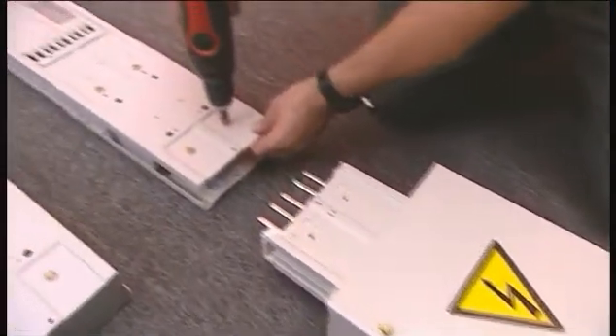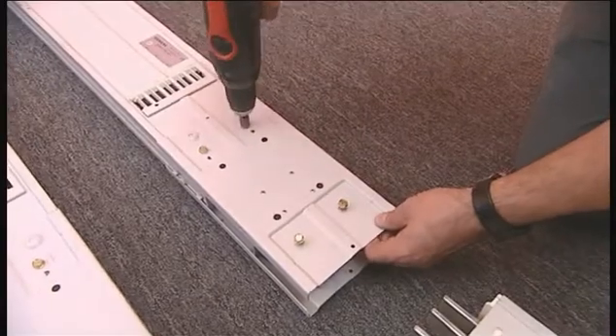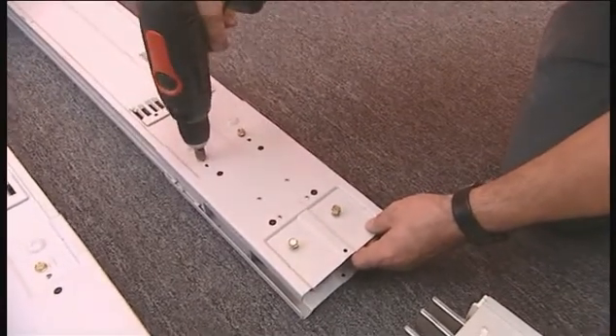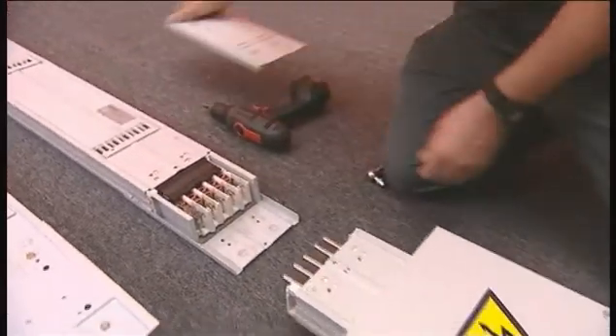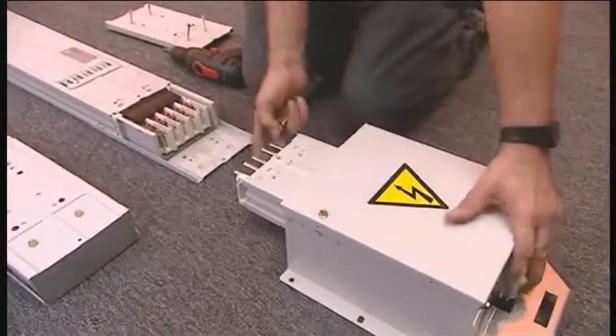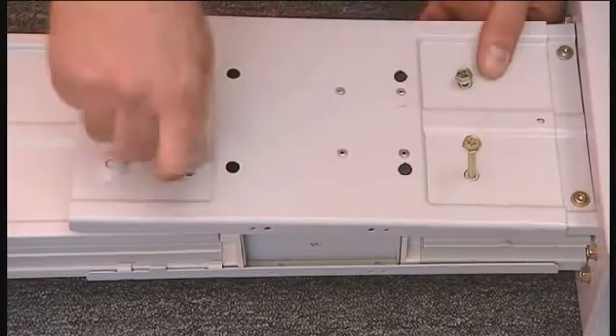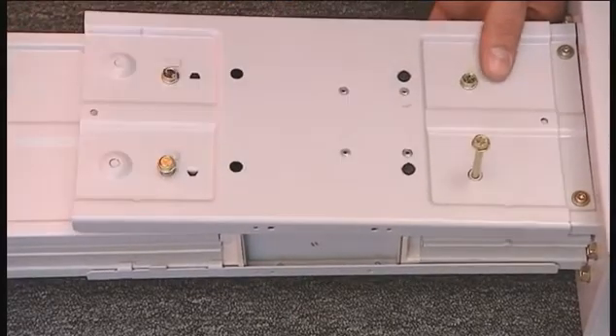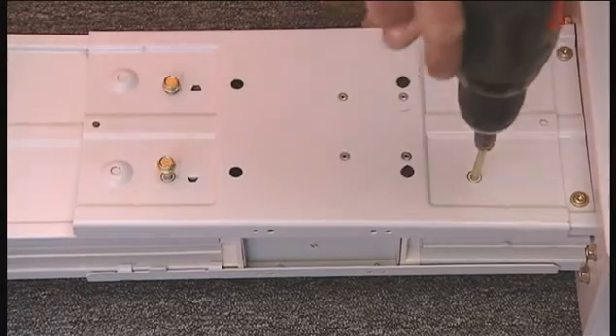After the feeder unit is closed, the plug-in terminal is prepared for installation by loosening the four screws and removing the flange cover. The plug-in terminal of the trunking unit is installed into the connection unit. The flange cover is closed by tightening the four screws. The maintenance-free electrical and mechanical connection is now established.